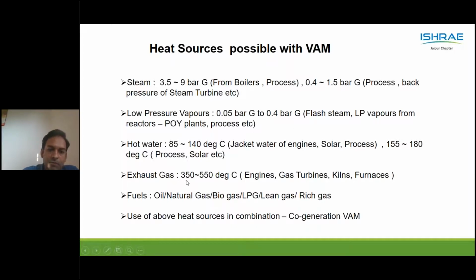Exhaust gases from 350 to 500. The important criterion is the composition of the exhaust gases. There should be no sulfur content, and they should be easily transferable to vapor absorption machines. Earlier, VAMs were designed on oil and natural gas as fuels. Now oil has become $10 per barrel, so hopefully in some part of the globe we'll have vapor absorption machines running on oil also.